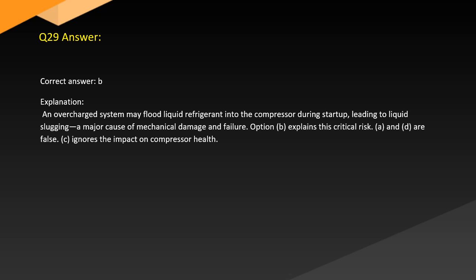Answer. Correct answer. B. Explanation. An overcharged system may flood liquid refrigerant into the compressor during startup, leading to liquid slugging, a major cause of mechanical damage and failure. Option B explains this critical risk. A and D are false. C ignores the impact on compressor health.